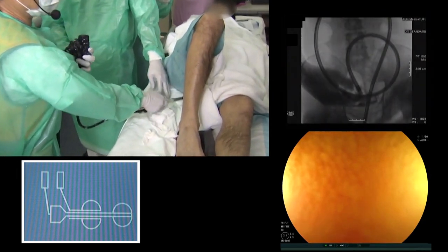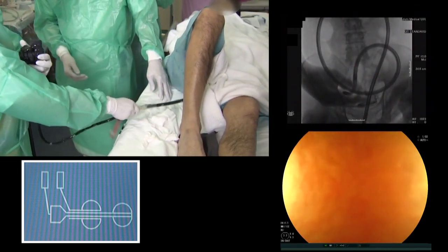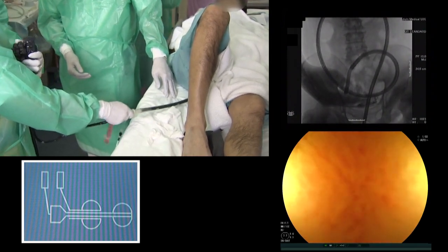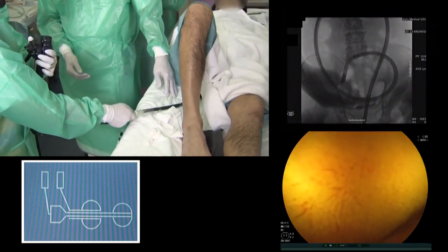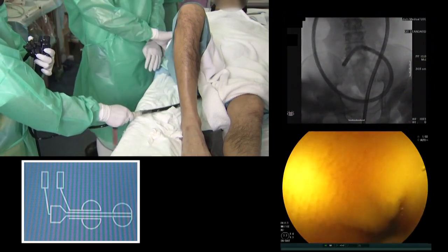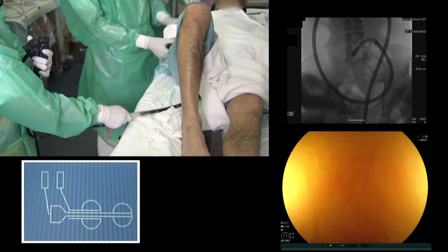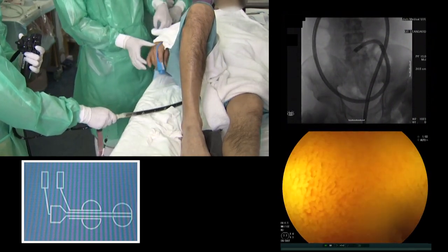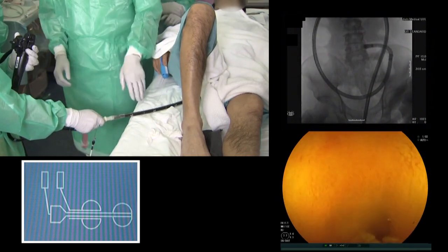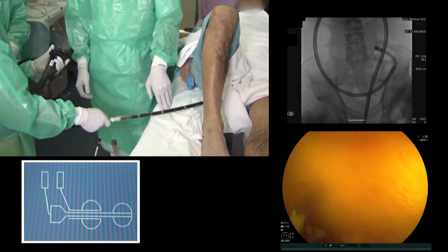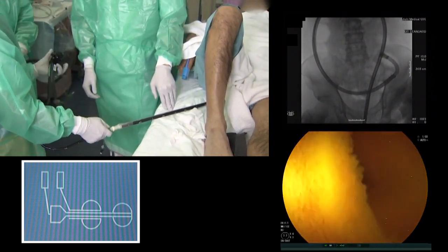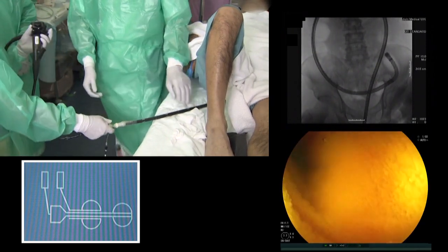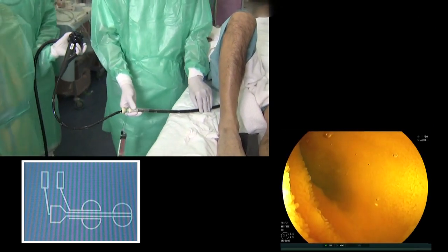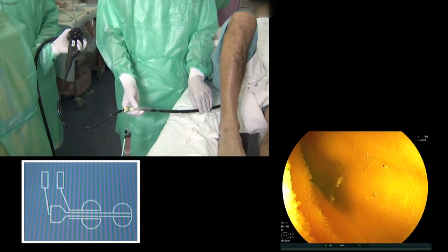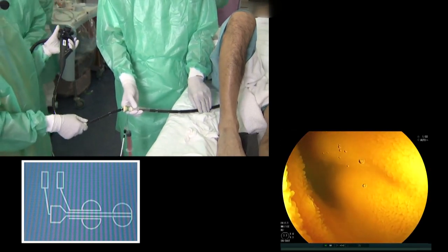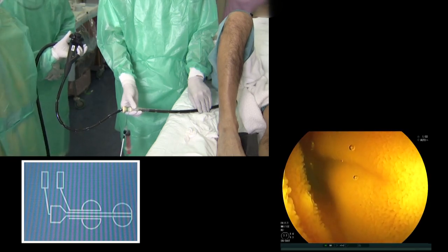Forcibly pushing it in this situation would only make it difficult, so you should advance the overtube and shorten it first, meaning you adjust the shape before the next advancement. So while shortening, you can recover the concentric circle shape again. You can perform this action without the endoscope slipping back to an excessive degree because it is secured by the balloon. Even if you see on the monitor that it is slightly sliding or coming out, do not worry. It is much more important to adjust the shape. Adjusting into a simple shape enables an efficient advancement and will compensate for the small distance lost by the endoscope slipping back.